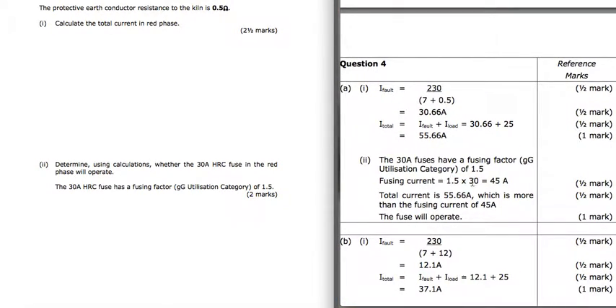Now we're going to determine whether the 30 amp HRC fuse is going to blow, is going to operate. Now the fuse has got a fusing factor, we're told, of 1.5. So that means it won't blow at 30 amps, it won't blow at 35 amps, it will blow at 1.5 times 30 amps. And 1.5 times 30 over here is 45 amps. So we need 45 amps for that fuse to blow. We've got a total current of 55.66, so the fuse will operate. So you need to show the calculation of the fusing current. You need to state what the total current is, and you need to say that it will operate to get your maximum marks.